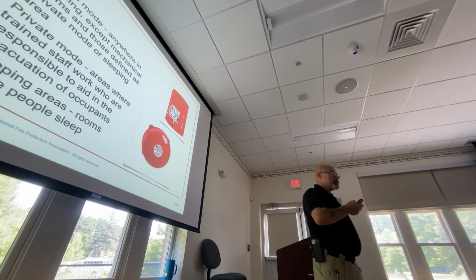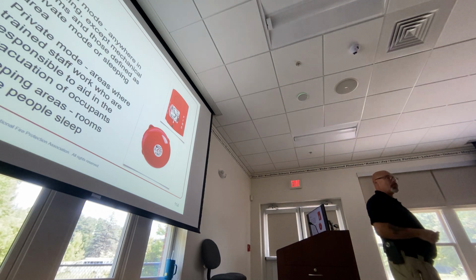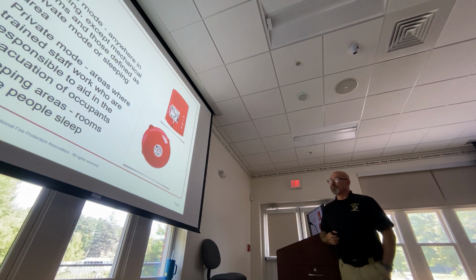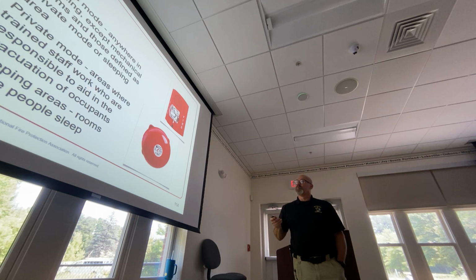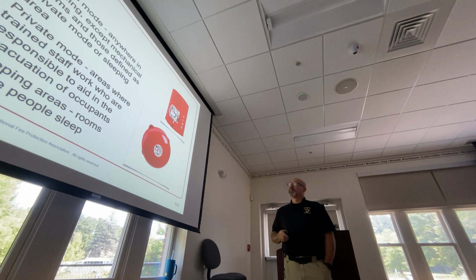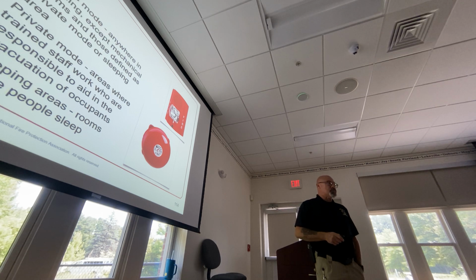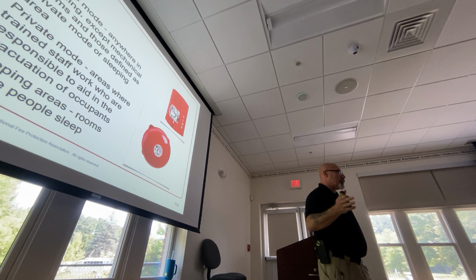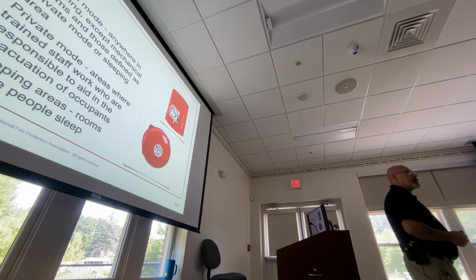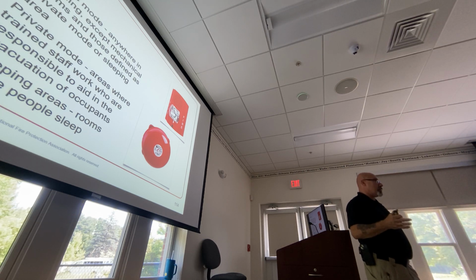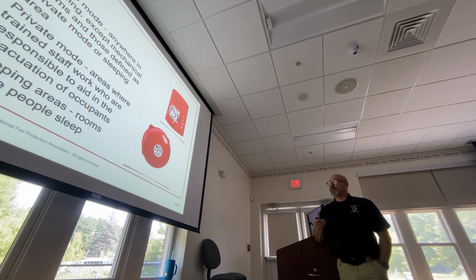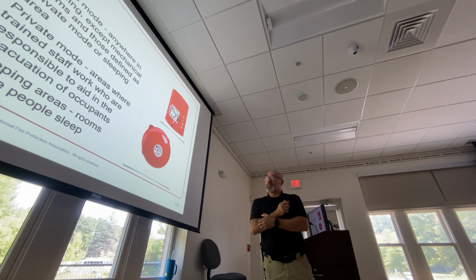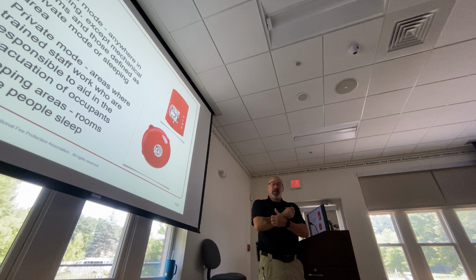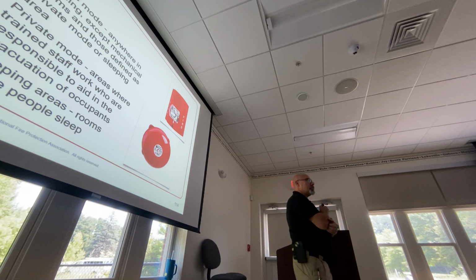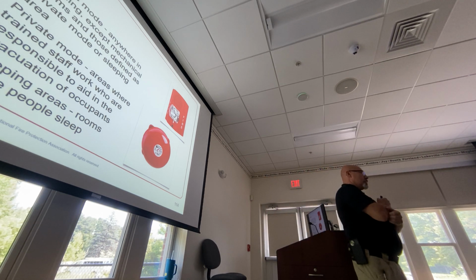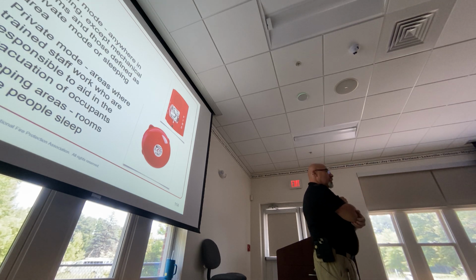So the audibility, the strobe itself or the alarm that's going off, there's two different versions. There's a public mode and then there's a private mode. Public mode is what we're all used to. Goes off anywhere throughout the building. Okay? Fire alarm goes off, you're all hearing it. Private mode, areas where trained staff work who are responsible to aid in the evacuation of occupants. Where would we see a private mode type alarm system? Hospital, nursing home? Hospital and nursing home.